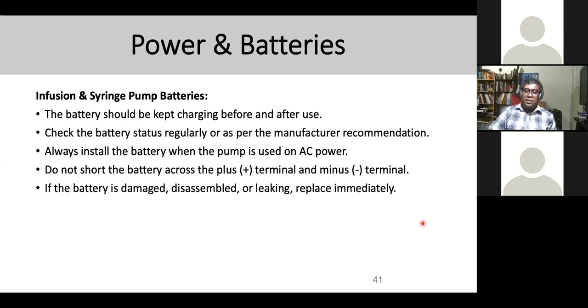Another important part is the power and the battery. So always keep the battery charging before and after use. The reason is that it's easy to access, with no need to charge at will, but make sure that you are prepared. Check the battery status regularly as per the manufacturer's recommendation. If you look at the user manual, they will leave some recommendations on the battery details, and always install the battery when the pump is used on AC power. Do not short the battery across the terminals. Sometimes they intend to remove it, so it can cause damage. And if the battery is damaged, disassembled, or leaking, replace it immediately.